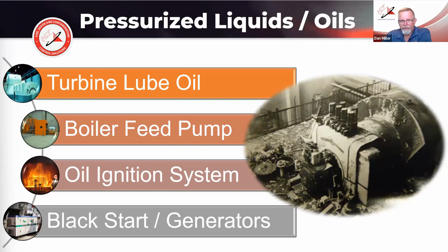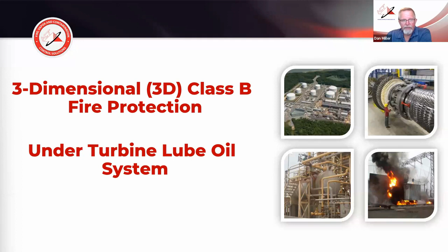feeding the boilers themselves, oil ignition systems, so you've got oil moving and flames, always a challenge to manage that, and black start generators that start up on their own as needed, can be a fire hazard as well with the fuels involved in those. So again, your under turbine lube oil systems are a three-dimensional Class B fire hazard. And when they do catch on fire, the fire is dramatic and intense. So you have to have a system, typically besides plain water, that can better manage that type of fire. So F500 has been proven to do that, and we'll talk about how that works in just a moment.